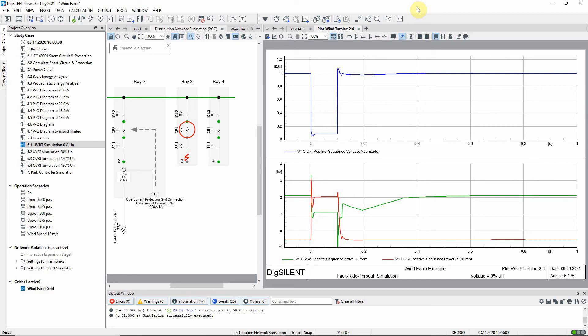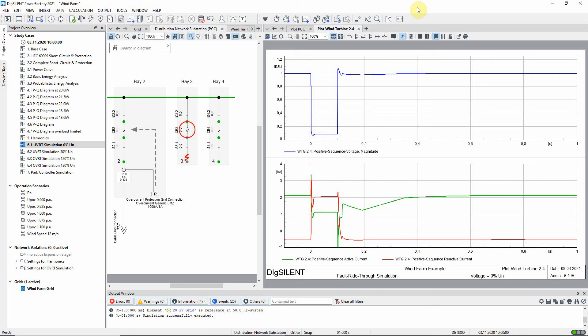As soon as the fault is applied, there is an initial reaction from the wind turbine. And then the voltage support mode for the fault ride through begins to exert its influence. The reactive current delivered is determined by the voltage dip and the K factor, and is increased. The active current is reduced, since priority is given to the reactive current injection. Post fault, the values return to their pre-fault values.